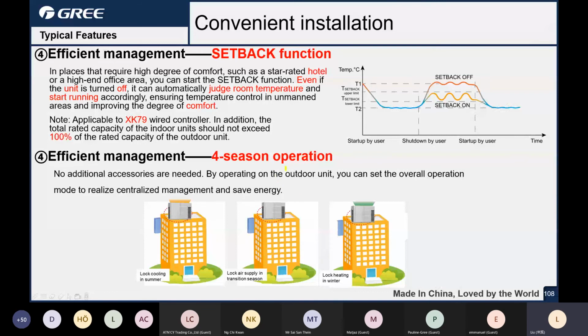Next one is the 4-season operation. That means you can shield the outdoor unit running mode in different seasons, such as you can just use cooling in summer. That means all of the indoor units cannot be switched to heating, to avoid misoperation by some spoiled child, right? Or the air supply in transition season, just turn on the fan. Use the fan, no heating or no cooling in the transition season. Or in winter, lock the heating, cannot switch to cooling. Okay.